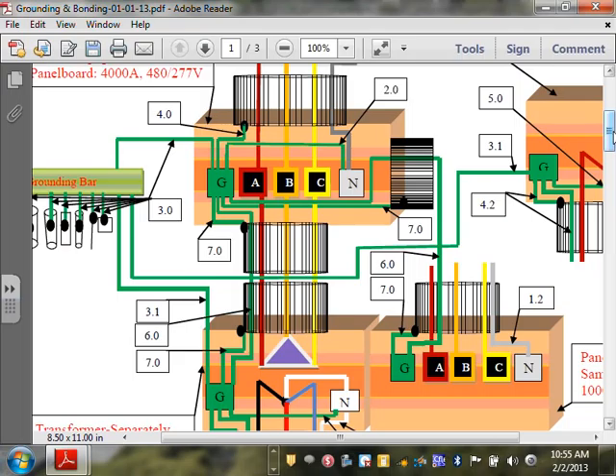Now here's where the issue becomes. Number 7 becomes very important to bond it if you're using the EMT conduit or the rigid as an equipment grounding conductor. If you're not using the number 6, then number 7 becomes very crucial to bond the conduit, bond it properly. Either way, you have to bond. Let me just tell you, either way, you have to bond it properly. How do you bond it properly? There are different ways of bonding, guys. You have to have bonding bushing, a wedge, bonding clamp on both sides.